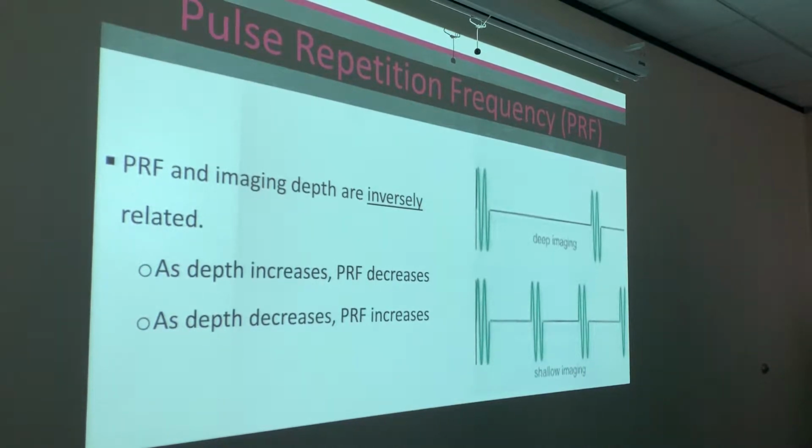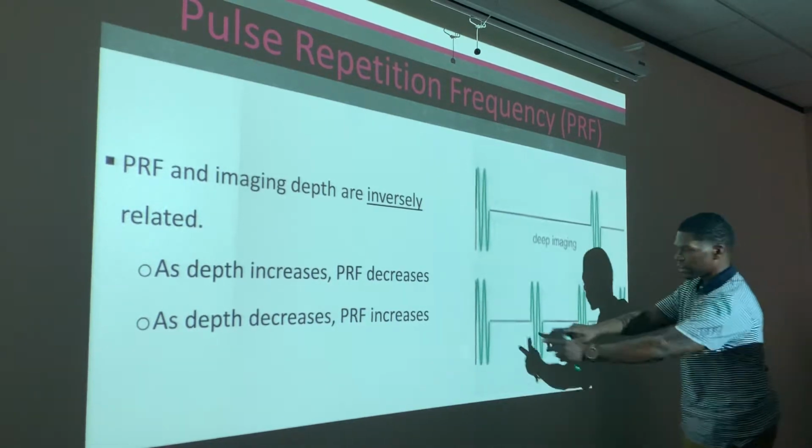When we change the PRT, we change just the listening time? That's it. Or the pulse? I just said you're never changing that. You're never changing the pulse. The pulse is the pulse is the pulse. Write that down. You're never changing that. You're only changing the listening time. Just this line right here, this is all you're changing.